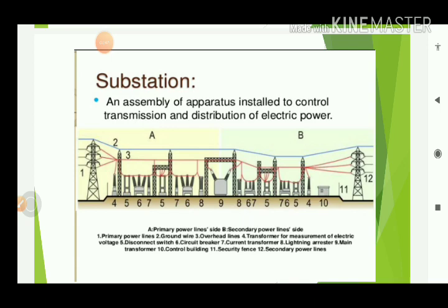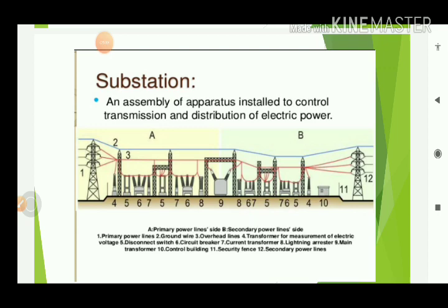Next is the circuit breaker — it is a protective device, which is very important. After that, the CT, known as current transformer, used for measurement and protection purposes. After that, LA — lightning arrestor — it is protection against lightning strokes. After that, the main transformer, which is the power transformer — the heart of our power system and substation. Next is the control building, where all the control panels are housed. Security fences are there for strictly prohibiting unauthorized persons and animals. Last is the secondary power lines at the outgoing end.